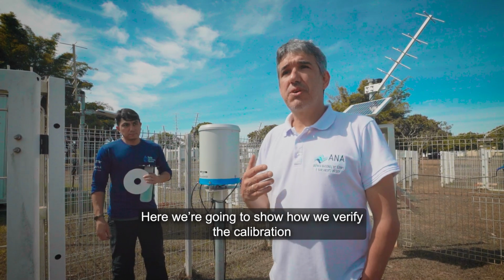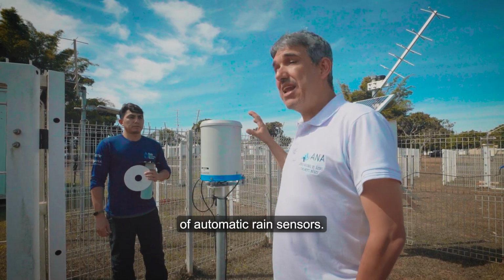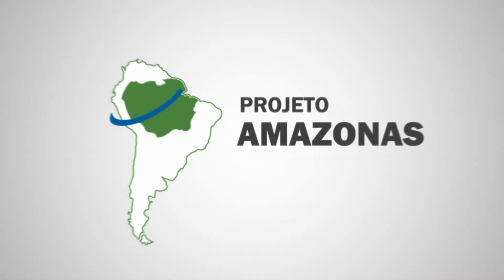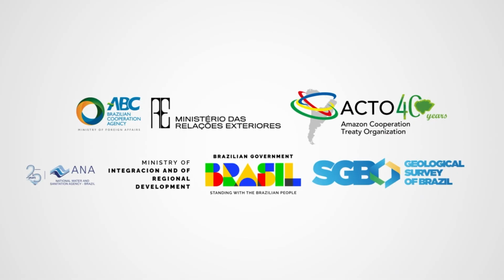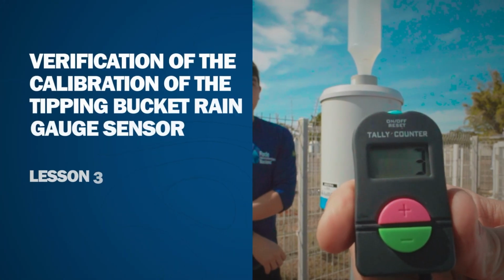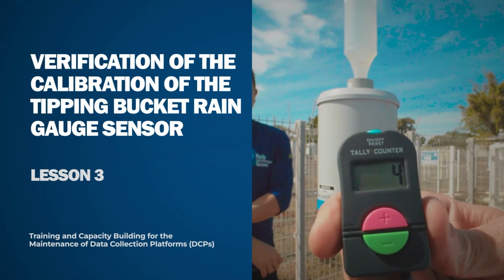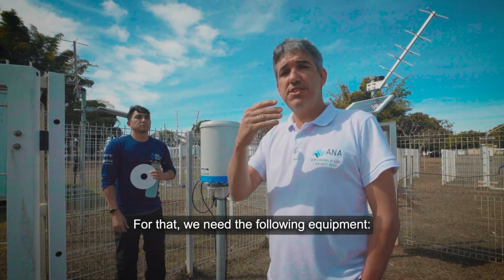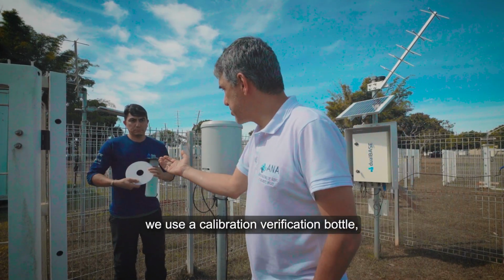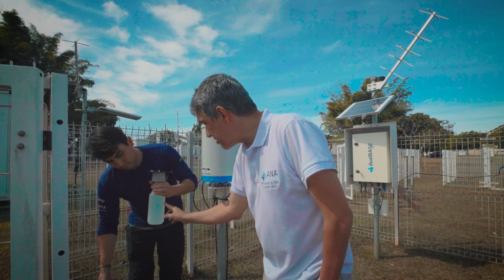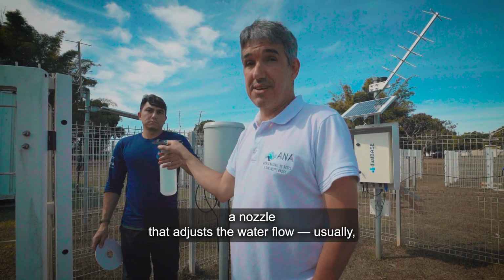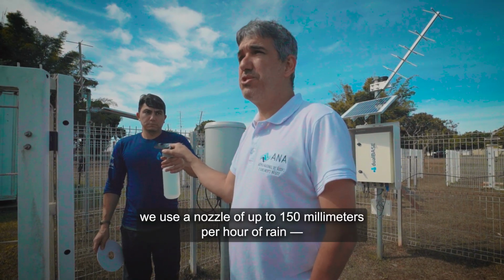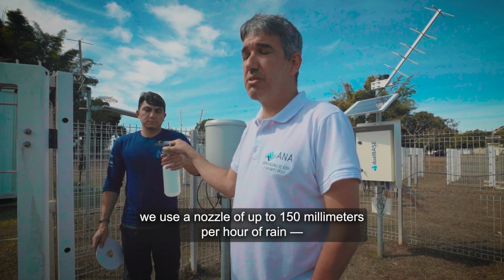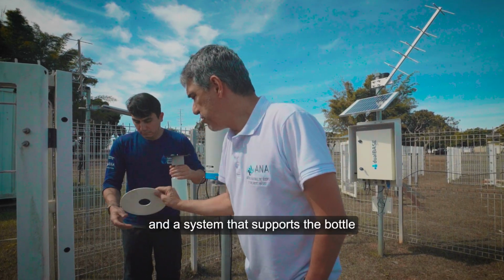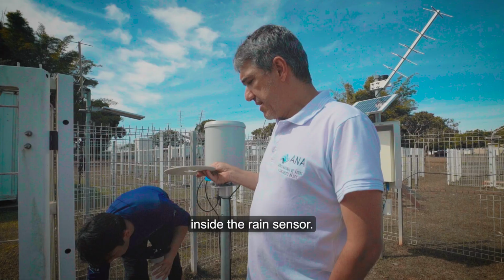Here, we're going to show how we verify the calibration of automatic rain sensors. For that, we need the following equipment. We use a calibration verification bottle, a nozzle that adjusts the water flow. Usually we use a nozzle of up to 150 millimeters per hour of rain, and a system that supports the bottle inside the rain sensor.